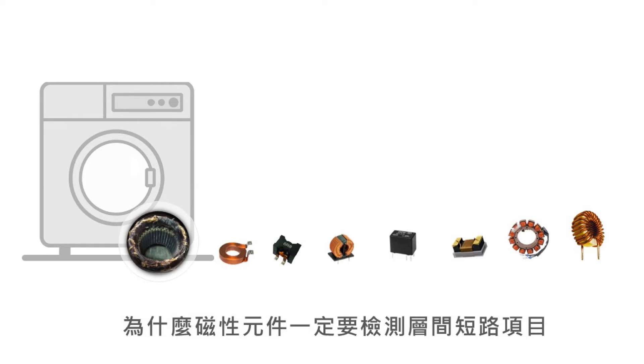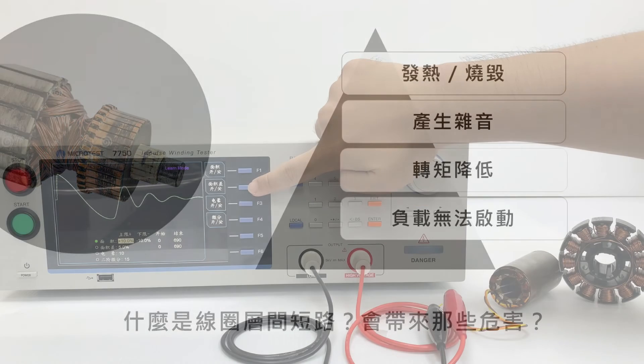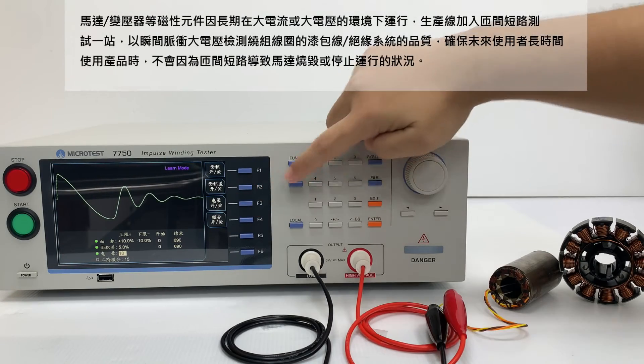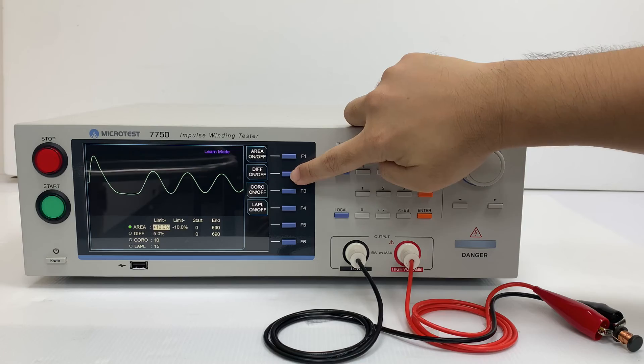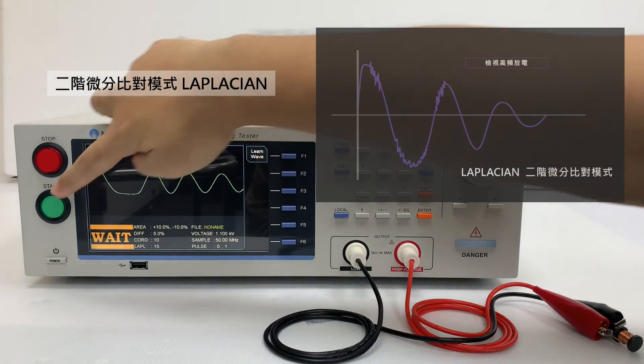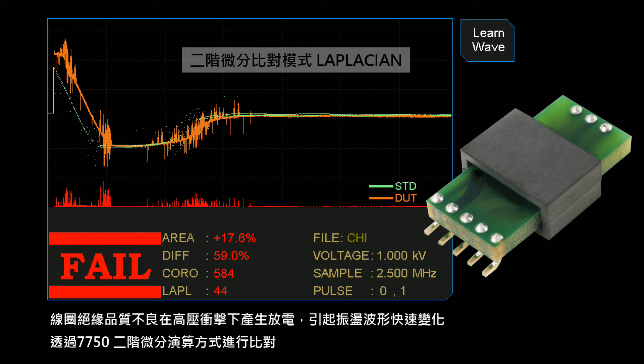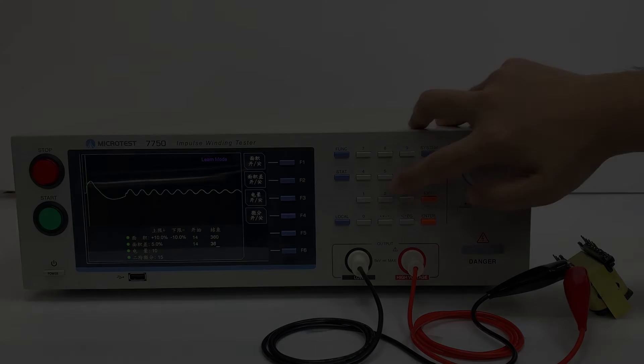The importance of impulse testing: recently, the voltage on electronic products has been increasing. Partial discharge may happen under instant high voltage, causing current leaking, which may cause penetration of the wire insulation. Short-time withstanding tests are not able to detect the product life of a transformer. So, the inspection by impulse test is necessary.